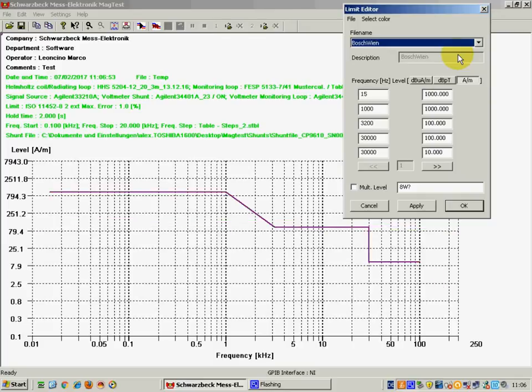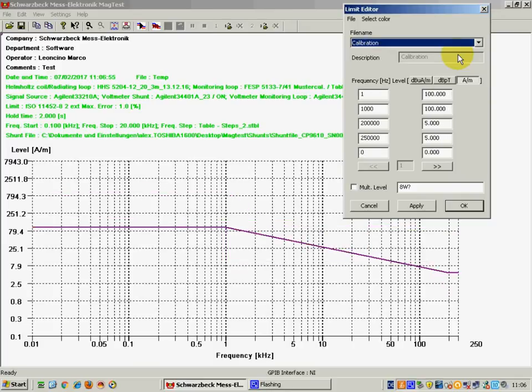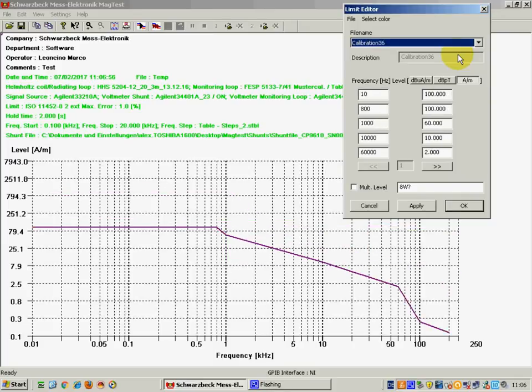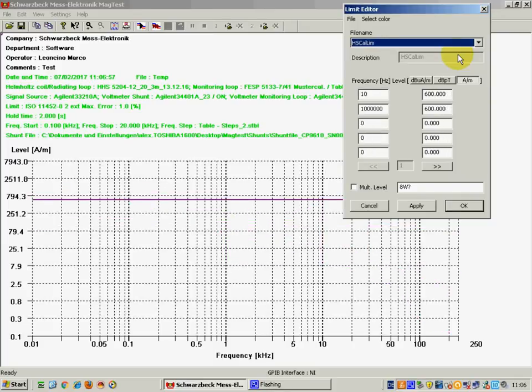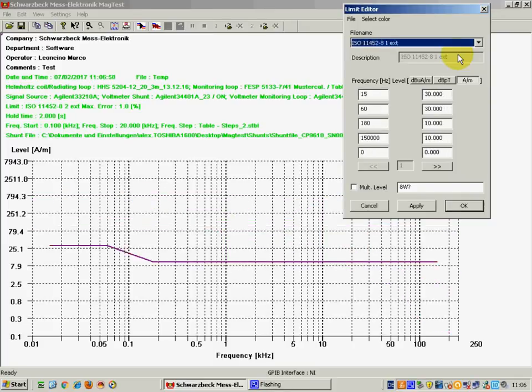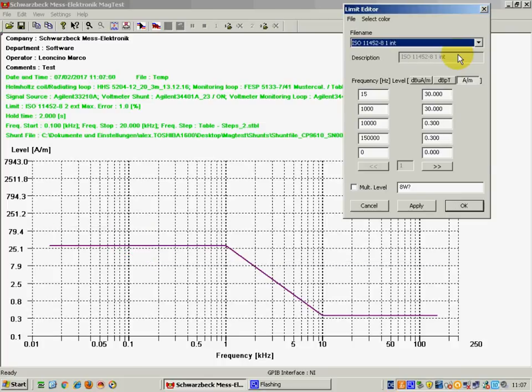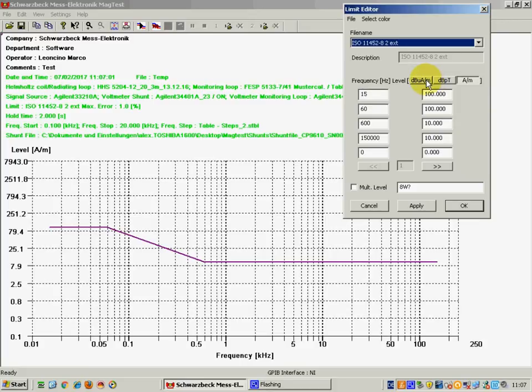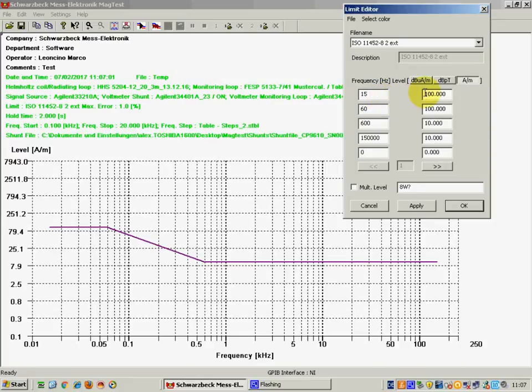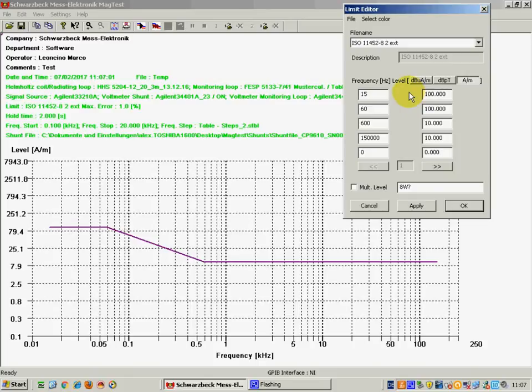In particular, a very well defined standard defines the frequency and the corresponding level in ampere per meter or in different units of measurement. In this case you can see the frequency on the left of the panel and the corresponding field strength in decibel microampere per meter, decibel picotesla or ampere per meter. In this case you can also have the option to set up your own limit according to your own testing.